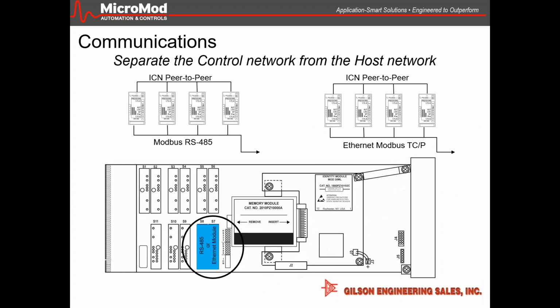With the peer-to-peer and Modbus, you have the ability to talk back and forth between the instruments, use the signal that might come into one instrument, and of course ship it off to just one other instrument, or maybe 2 or 3 or 4 or 5 that might be in the network. And then you're able to take that information and tie it to an HMI, tie it to a SCADA, bring it to a building control system through either Modbus or Ethernet.